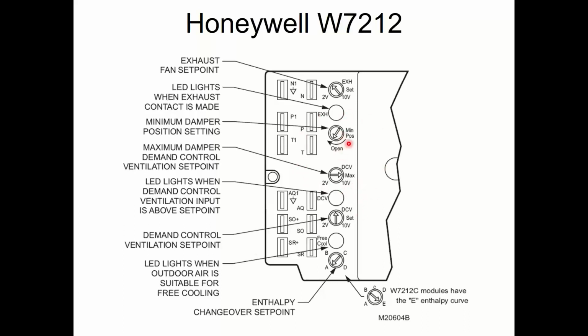But when you have DCV, the basic premise is instead of this being a minimum position and this being a max, let me get out my pen, it becomes a new minimum. So if you remember, like say for an office building, we required 5 CFM per person and we required 0.06 CFM per square foot, and I made you add them together. And you probably wondered why did they just do it, add it for me? Why is it separate? It's separate since 2004 for ASHRAE and 2006 for the mechanical code on purpose and specifically to aid in demand control ventilation.